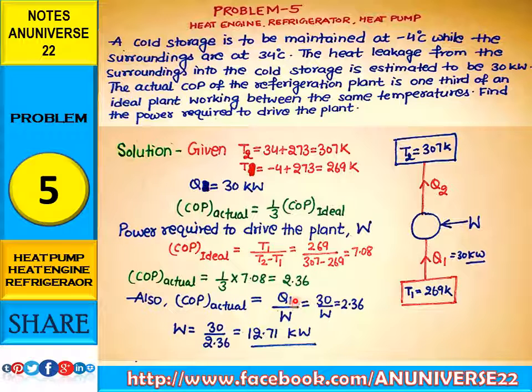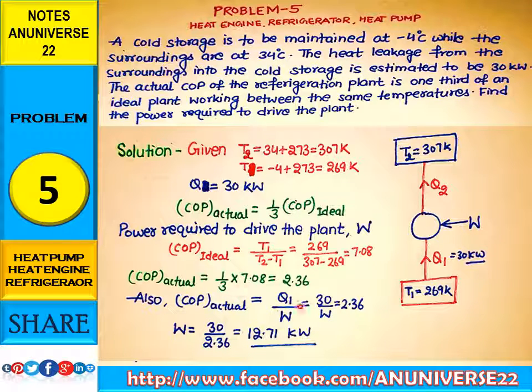COP actual equals the refrigeration effect divided by work done. Q1 is given as 30 kW and COP actual is 2.36, so W equals 30 divided by 2.36, which gives 12.71 kW. This is the power required to drive the plant.